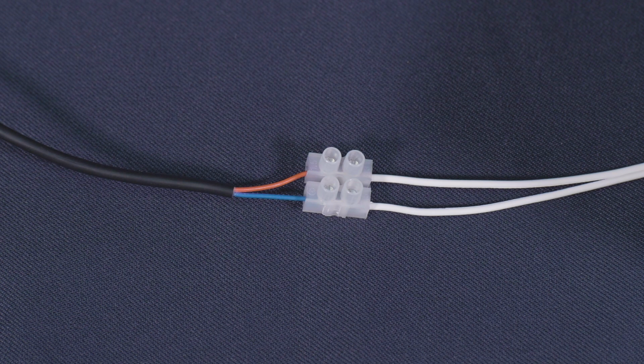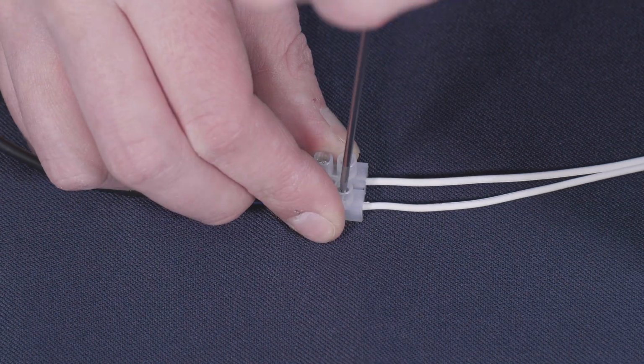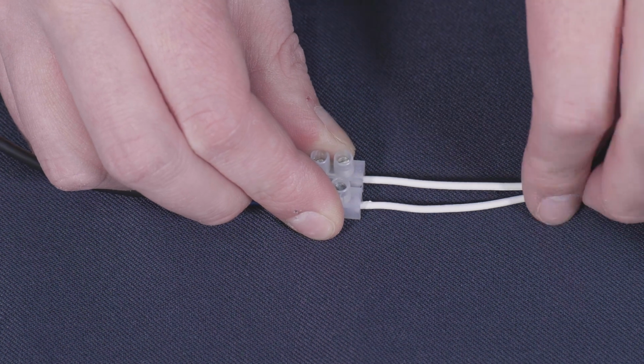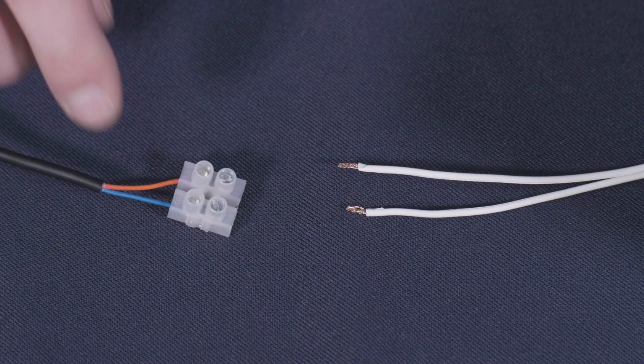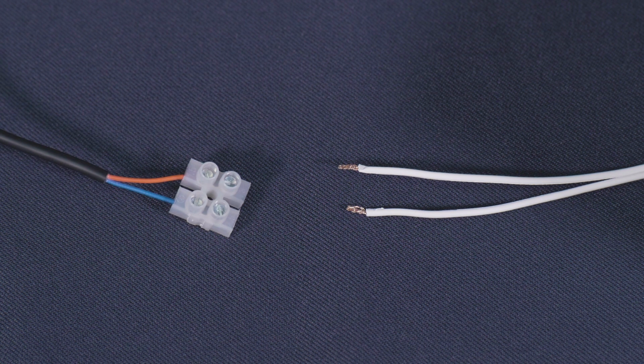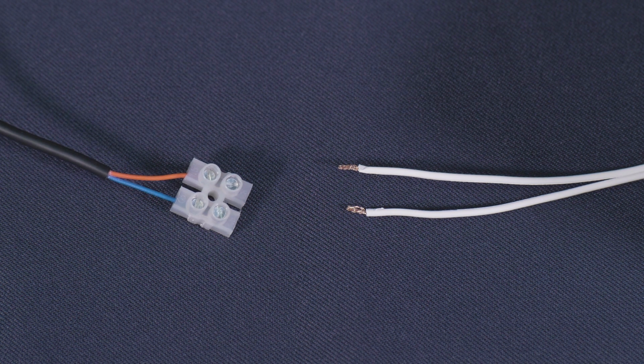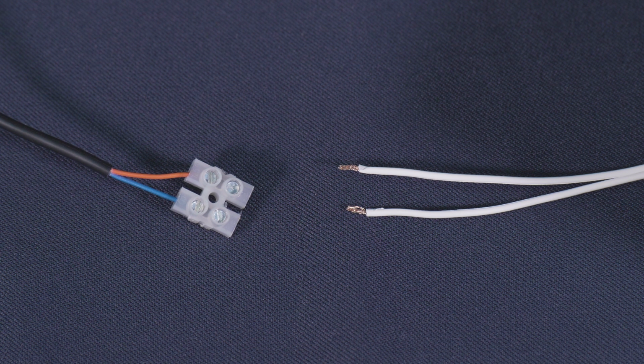If the pump turns on and does not switch off, the test we need to carry out is to disconnect the bell wire from the connector block while the pump is running like so. After a few seconds, the pump should stop. If the pump does stop, please check the flow switch as shown earlier in this video. If it does not switch off, it may mean the transformer has failed and needs to be replaced.